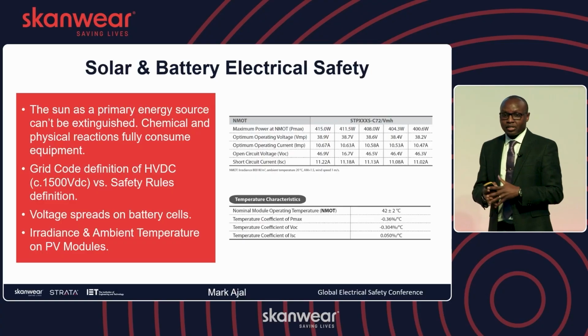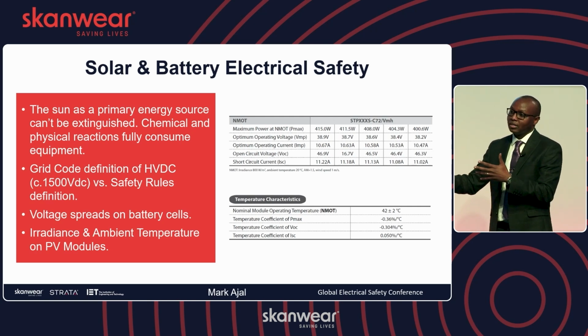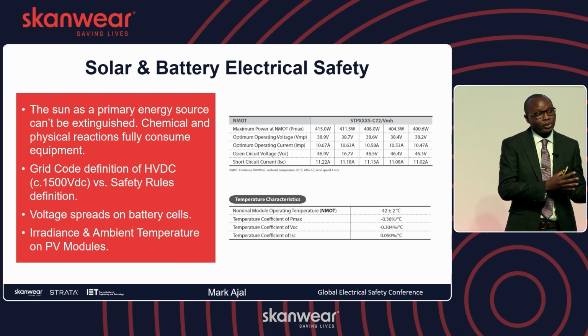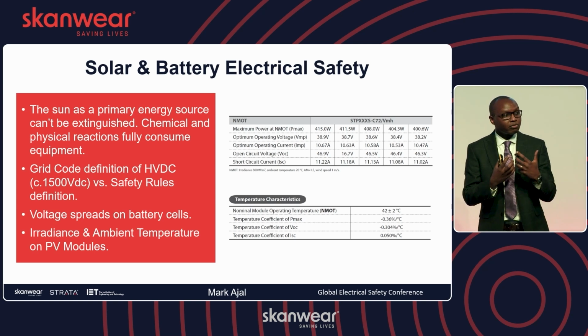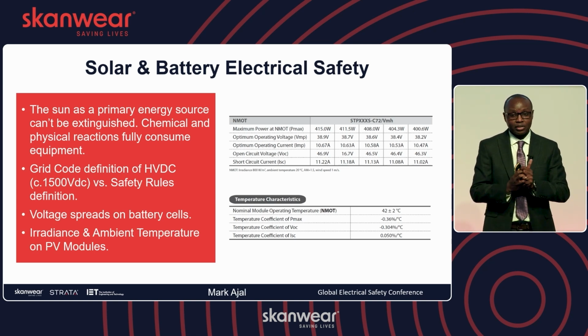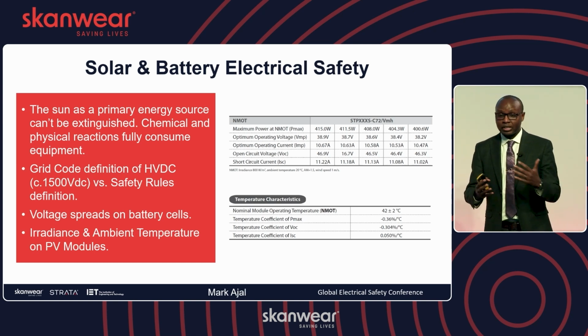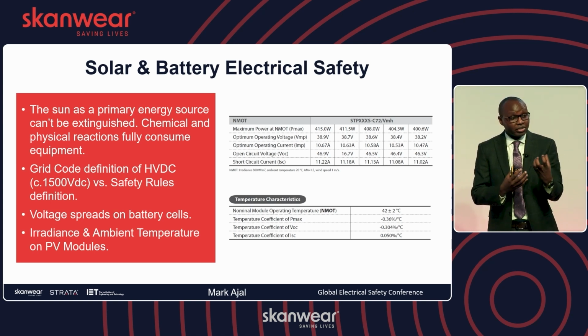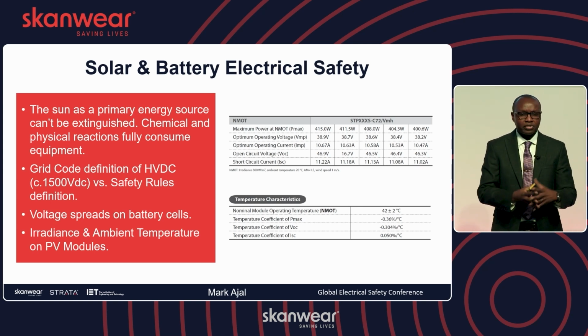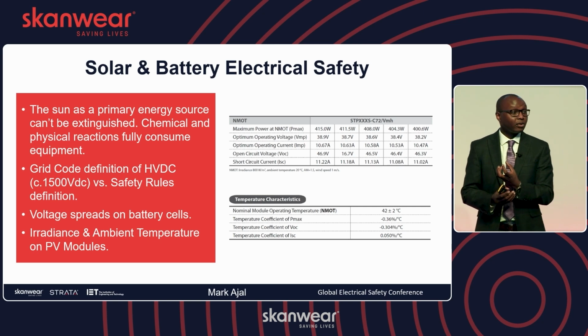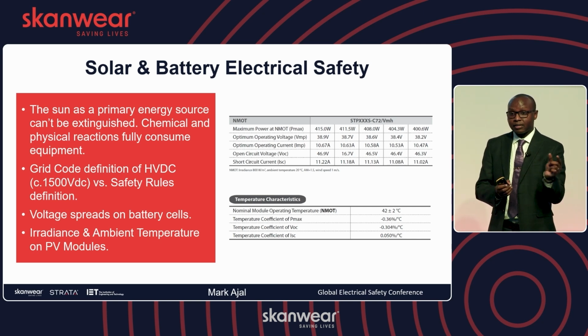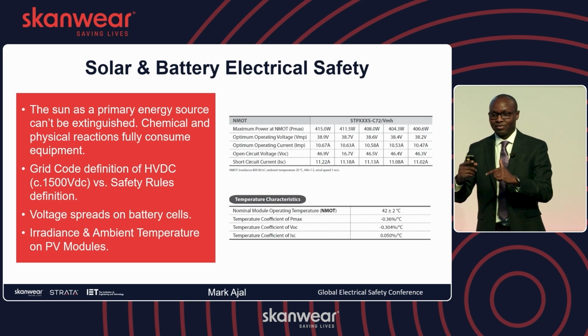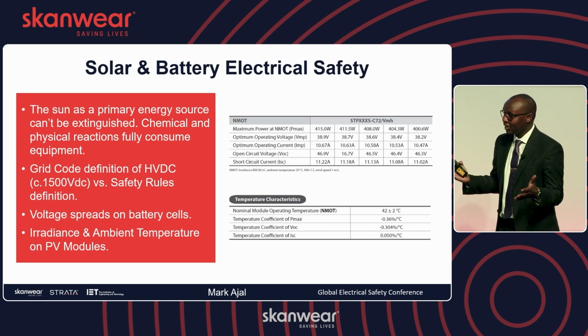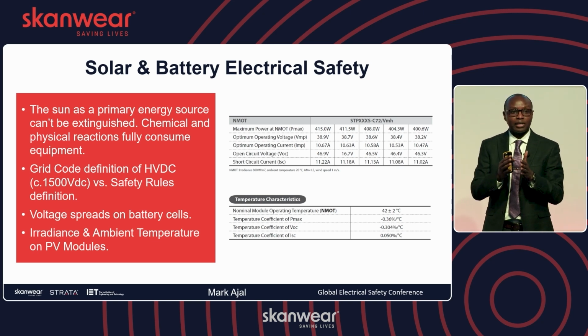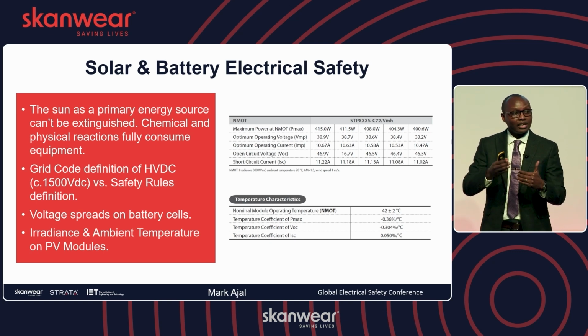Another challenge that we face in emerging technologies: grid codes were traditionally written for the traditional power conversion systems, coal, gas, lignite, hydros to electricity. Grid code definitions sometimes don't fully capture the essence of dealing with DC systems. In other cases, safety rules of different companies, it's a global conference, would touch very heavily on the AC component. There might be IEC standards that deal very strongly with AC, but perhaps are thin on the DC side. You'll find language like not exceeding 1,500 volts, and then exceeding 1,500 volts. That 1,500 volt threshold becomes your HVDC limit. Below that is LVDC, above that is HVDC.